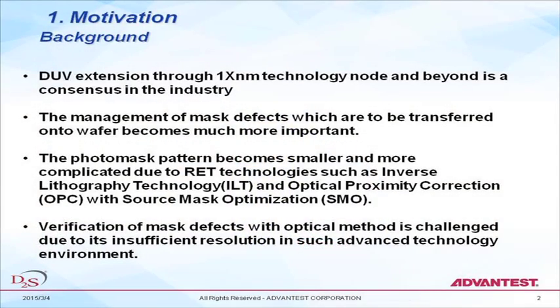Today's talk is focused on defect verification review. The motivation is that DUV extension through 1x nanometer technology node and beyond is a consensus in the industry, so management of mask defects that are transferred onto the wafer becomes much more important. The photomask pattern becomes smaller and more complicated due to advanced techniques such as ILT and OPC with SMO. Verification of mask defects with optical methods is challenged due to insufficient resolution in such advanced technology environments.